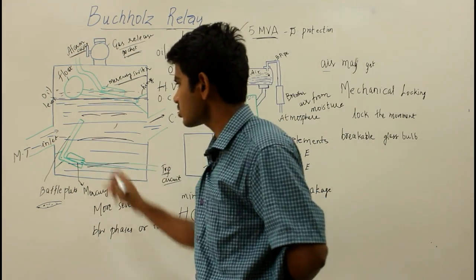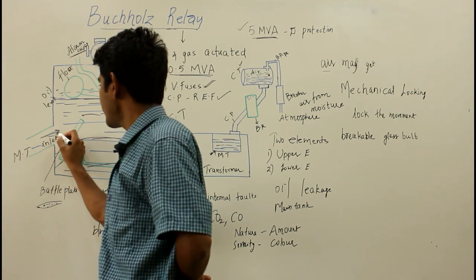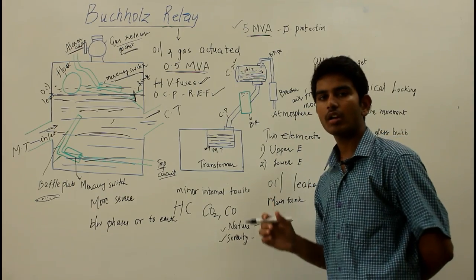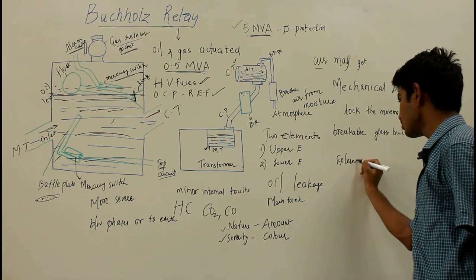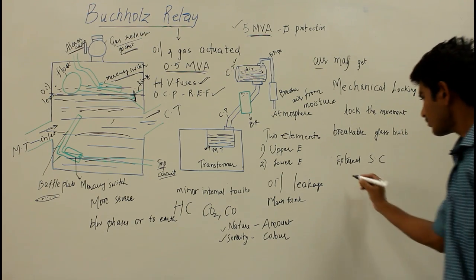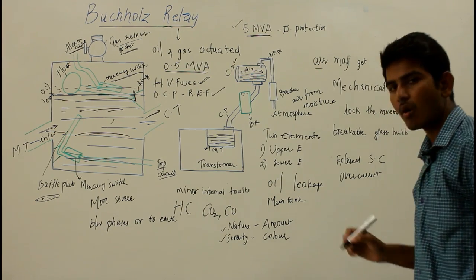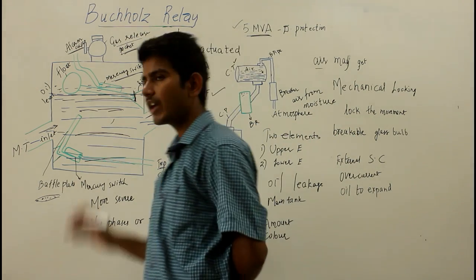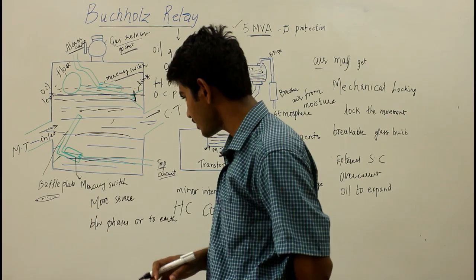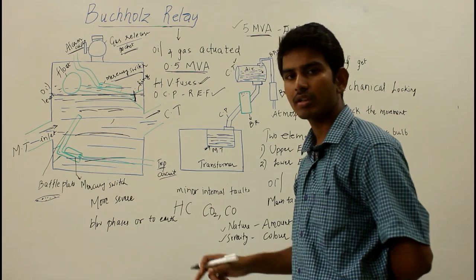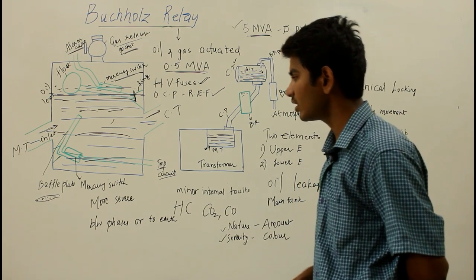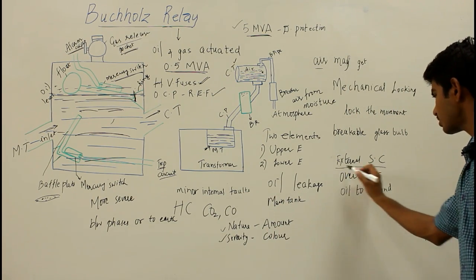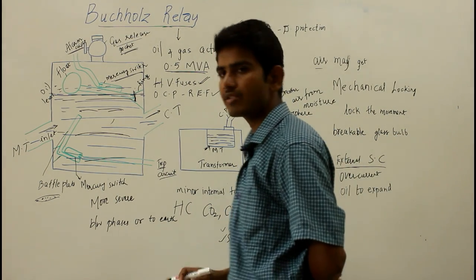The lower element may also falsely operate when there is high oil velocity striking the baffle plate even though no severe fault is occurring in the transformer. This may happen in the event of an external short circuit, where overcurrent causes overheating in the copper and oil expansion. If the expanding oil strikes the baffle plate with high velocity, it changes the mercury switch alignment, closes contacts, energizes the trip circuit, and isolates the transformer — causing a false Buchholz operation.